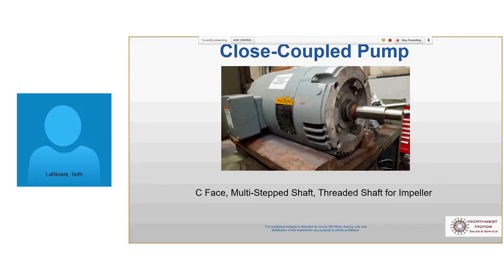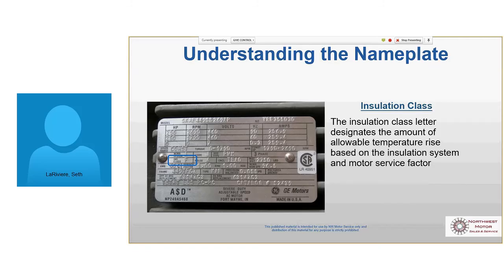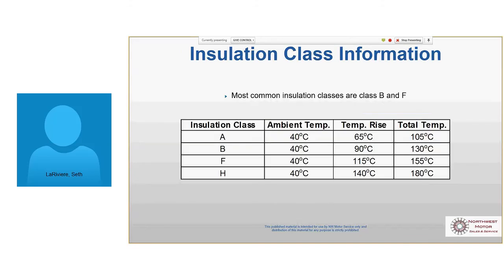So, insulation class, back to nameplates here, class F, that'll be on the nameplate. All manufacturers have to put that on. Oh, geez, this would have been nice to talk about when I was adding everything up earlier. So the B that we were talking about earlier: 40-degree ambient, 80 degrees rise, plus a 10-degree hot spot is your 90, for a total of 130. So for the 4 classifications there you can see, we were talking about with the B with H, it's this pattern right here, 180 and 130. And it's also interesting, they claim 90, but over half the ratings are underneath a class A rise. So GE's is pretty conservative. They don't say that, but when they actually do the tests on these, half of them are class A rise with class H insulation, which blows my mind.